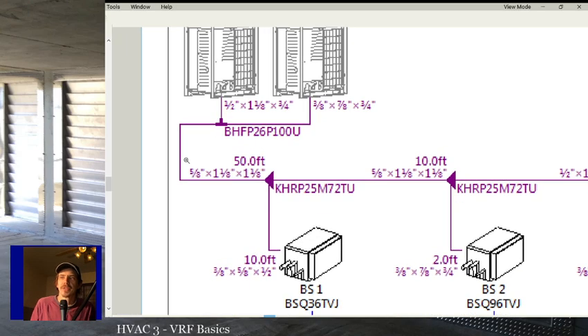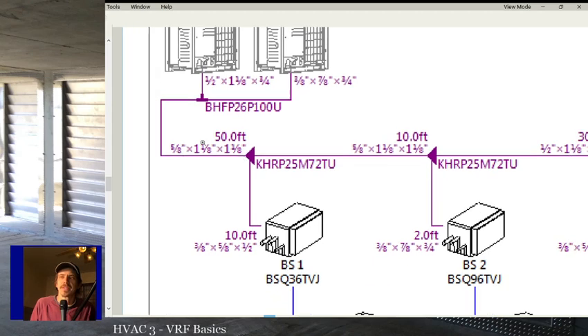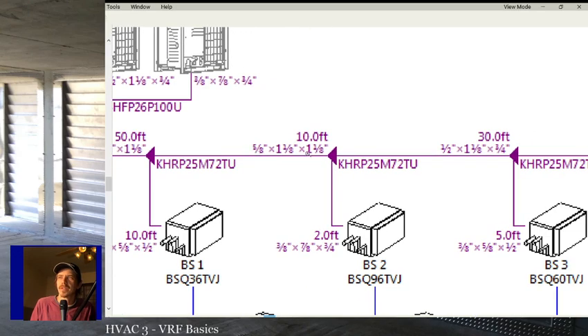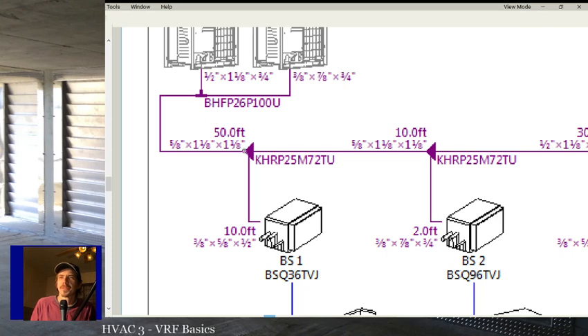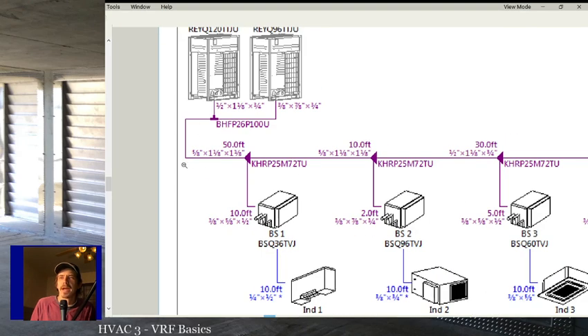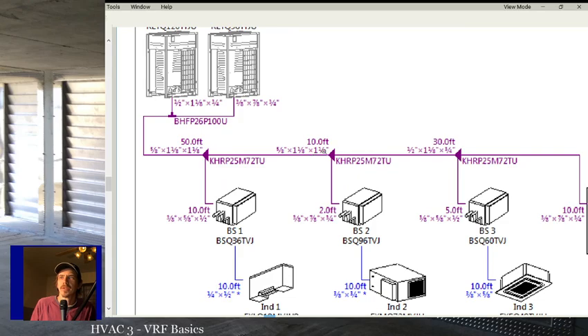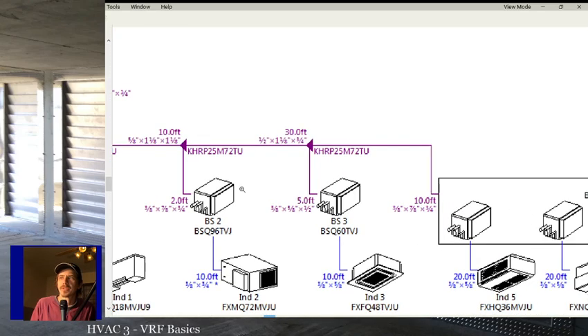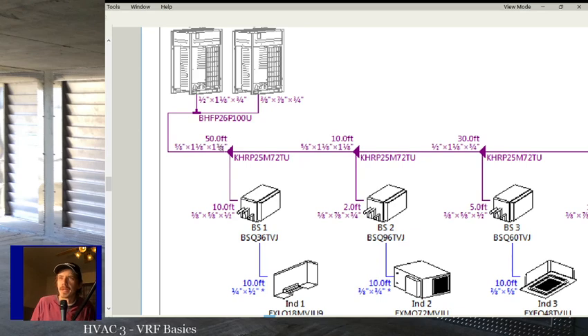I say that as you look at the main on this one, it actually turns into 5/8 by an inch and an eighth by an inch and an eighth, and it did end up the same size from here down to here for 2 units. So this system in particular that they have drawn out here actually ends up the same size for the high pressure, low pressure, and the suction line until it catches 2 units, and then they split up to different sizes again. So if those two are the same size, it can make it difficult to differentiate which one is supposed to be which. But you should be able to follow that line to somewhere where they're different sizes and figure out which one is the high pressure, low pressure gas line.